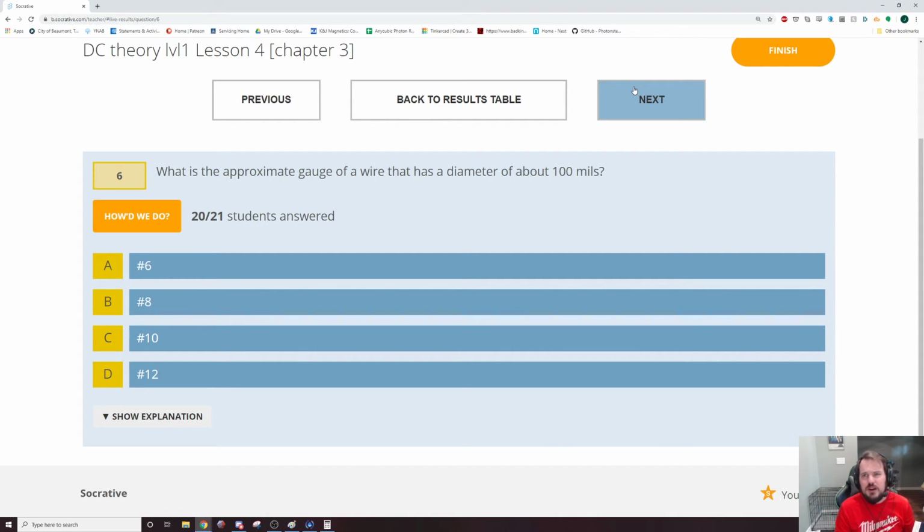So if you were ever out in the field and you were like, what size wire is this? There's no label. You could measure it, convert it to mils, square it, and then look it up in your code book. Probably somewhere around page 74, like Jacob would. Page 73. That's what I was thinking.